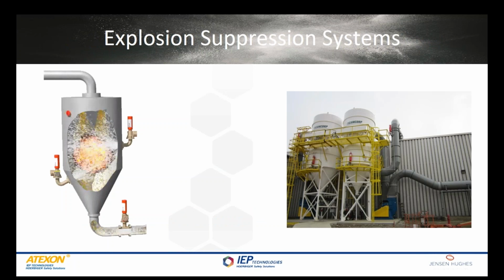Explosion suppression systems are another alternative to be considered. Explosion suppression systems work on the principle that during an explosion, you have a pressure that's growing at basically sonic speeds, something approaching 1,100 feet per second. At the same time, your flame speeds are somewhere in the vicinity of 3 to 10 meters per second initially. Now that speed will increase depending on geometry of the vessel and time. But initially, the flame speed is relatively slow in comparison to the pressure development rate.